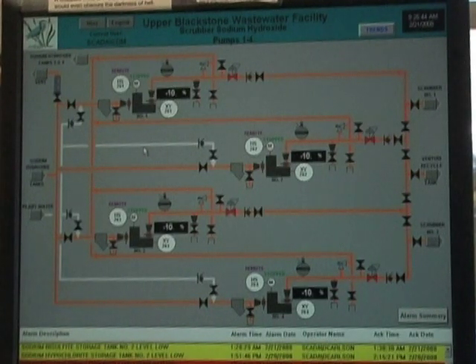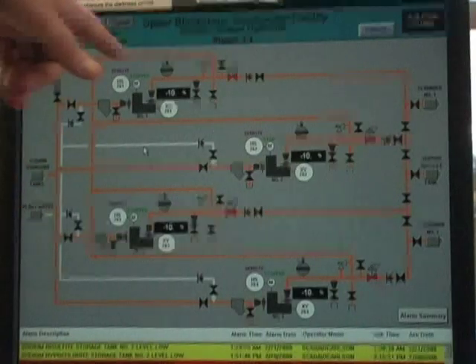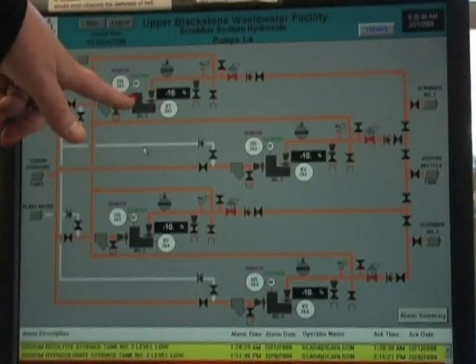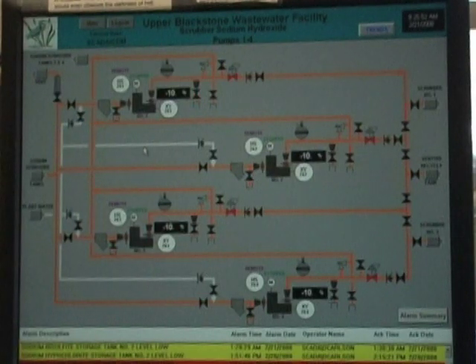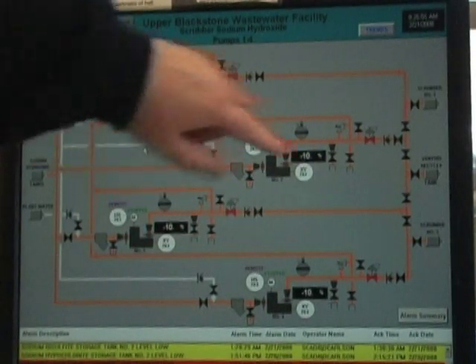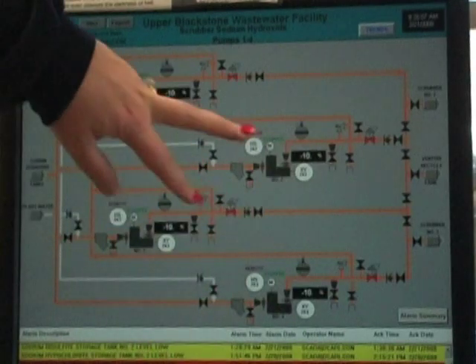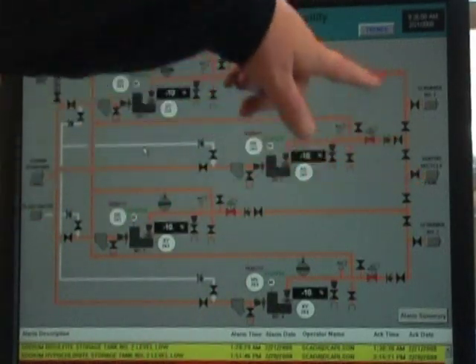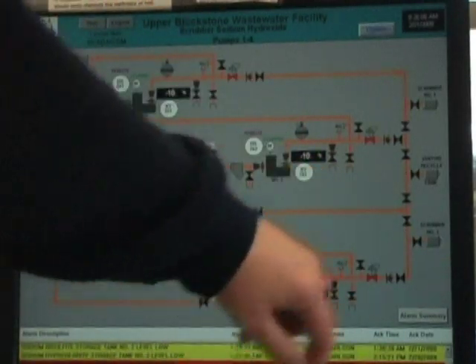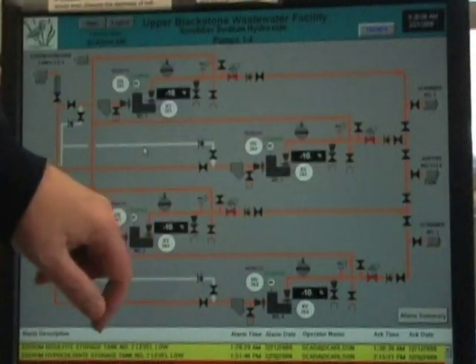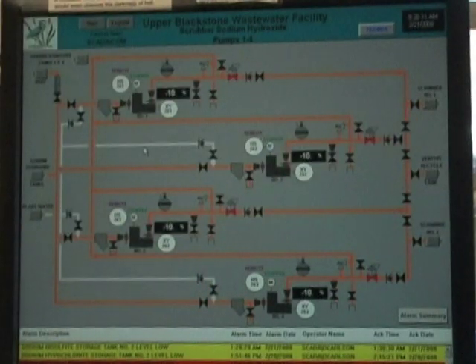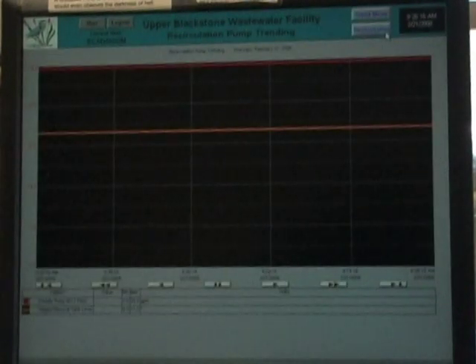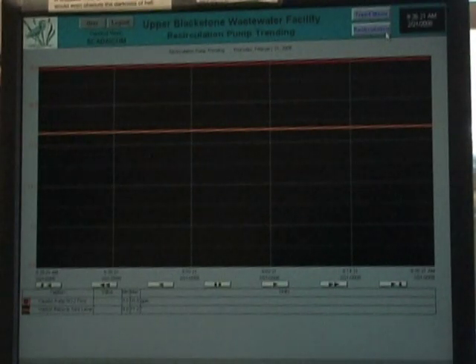In manual mode or in local mode, the valving can be switched around so that pump number 1 can feed scrubber number 3. However, in automatic mode, pumps 1 and 2 can go to scrubber 1 or the Venturi recycle. Pumps 2 and 3 can go to the Venturi recycle. Pump 2 can go to scrubber 1, pump 3 can go to scrubber 3, and pump 4 can go to scrubber 3 or the Venturi recycle tank. Pretty simple, straightforward. From here, we also have a trend screen that shows you the tank levels and the pump speeds, whichever pumps are running.